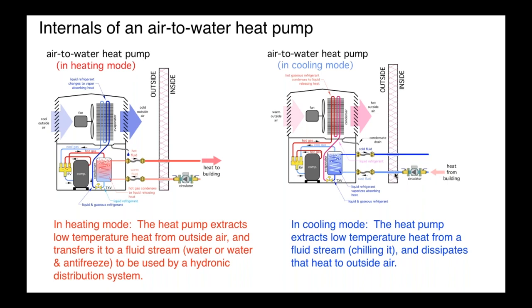So again, we have a stream here being pumped into what is now the evaporator in the heat pump, and that gets cooled, so we have the chilled water going back into the building for distribution, and then the heat is rejected outside. So that's a very basic four-component refrigeration system, very similar to the refrigeration concept used in geothermal heat pumps or even ductless mini splits, just a different physical configuration based on extracting heat, and dissipating heat to outside air and then tying into a hydronic distribution system.